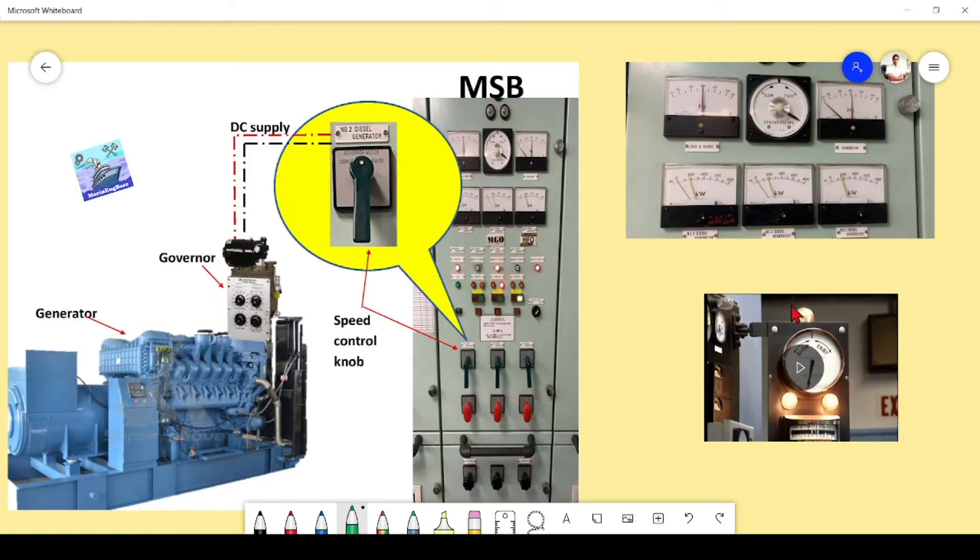The synchroscope is a device used to determine that the incoming generator and the running generator have fulfilled the principles of synchronization, and now the generator is ready to put into the bus bar. The breaker can now be closed, so that indication will be given by the synchroscope.